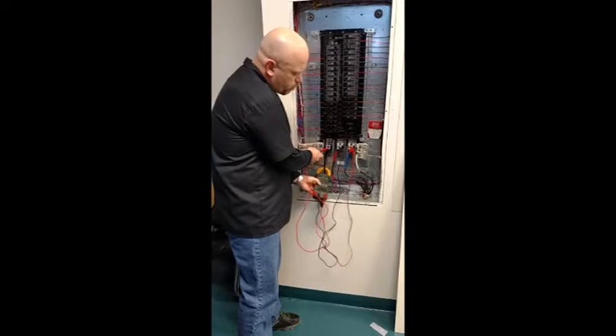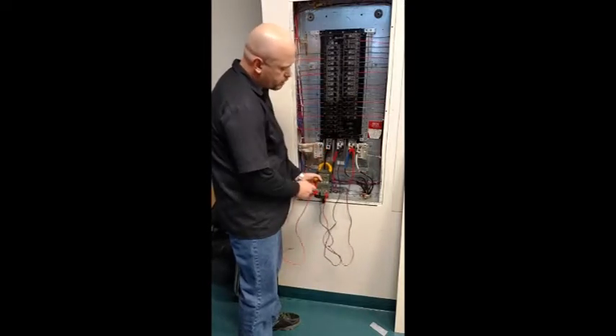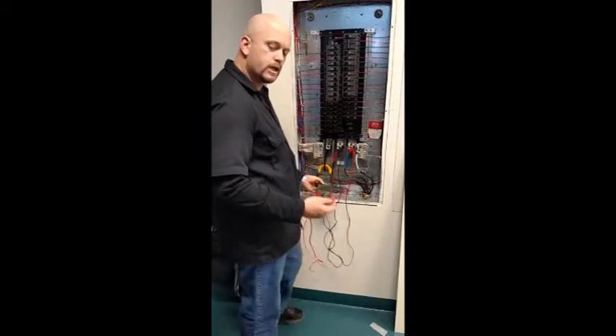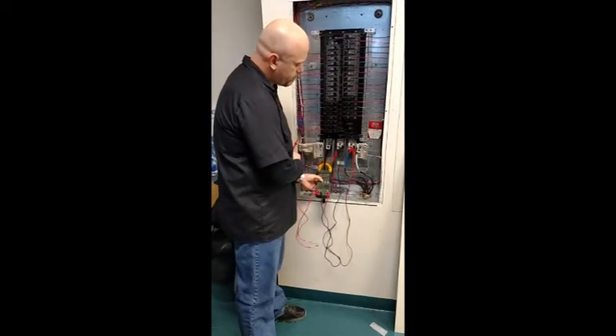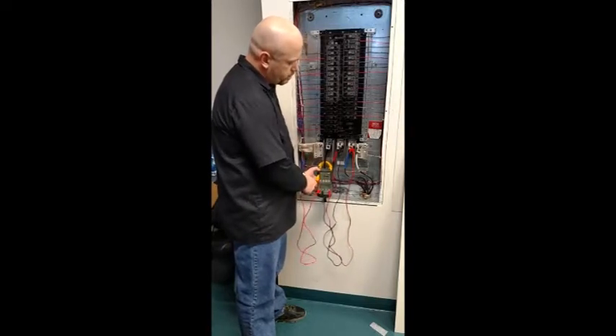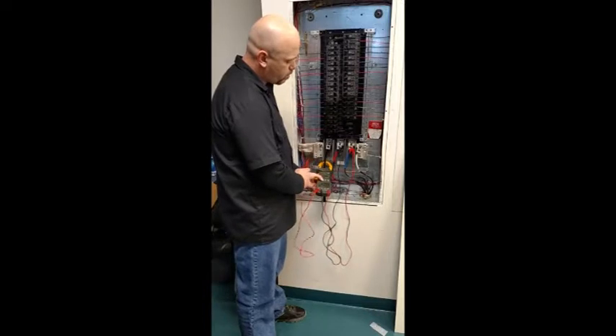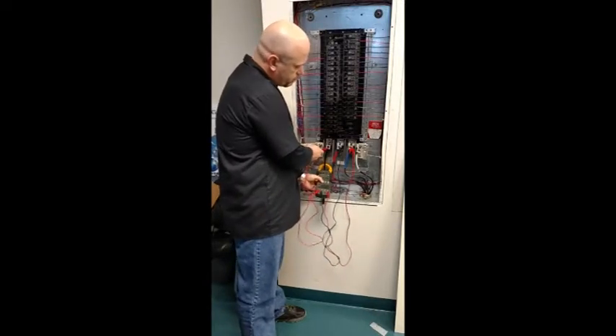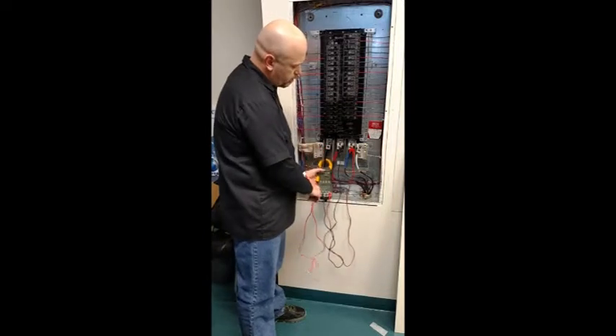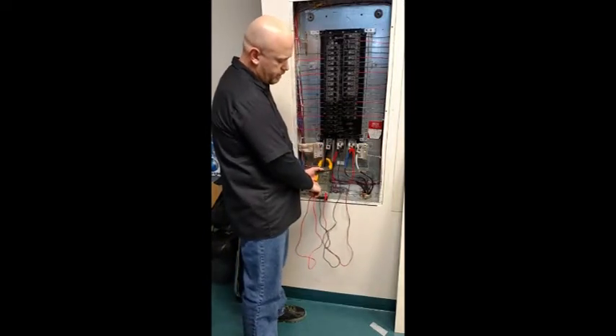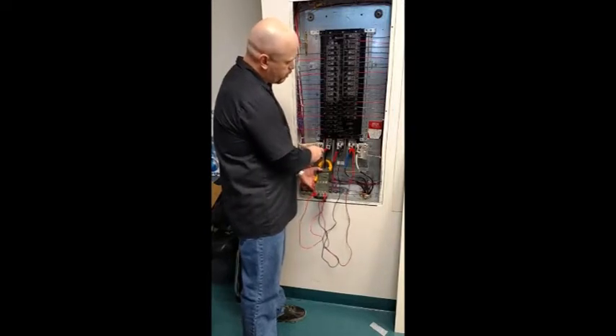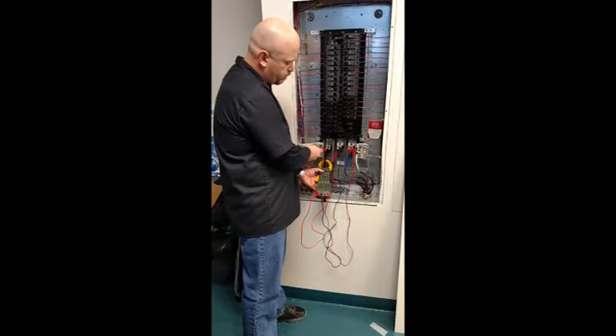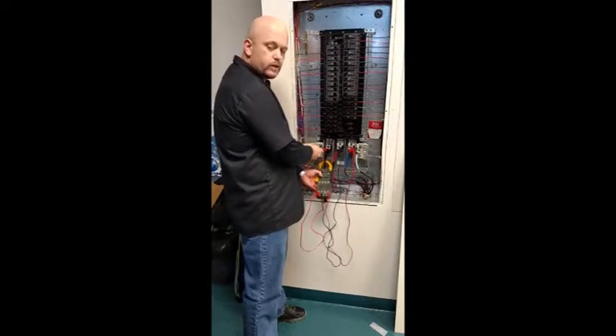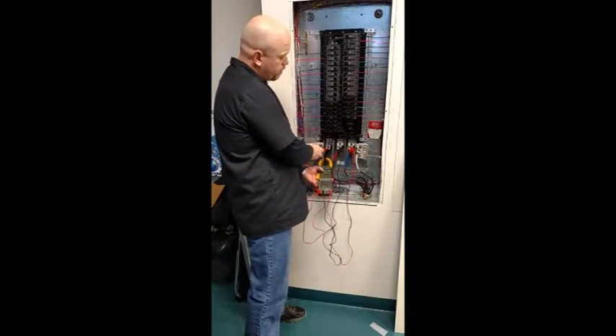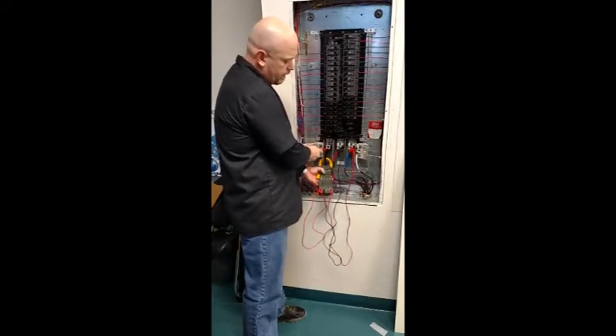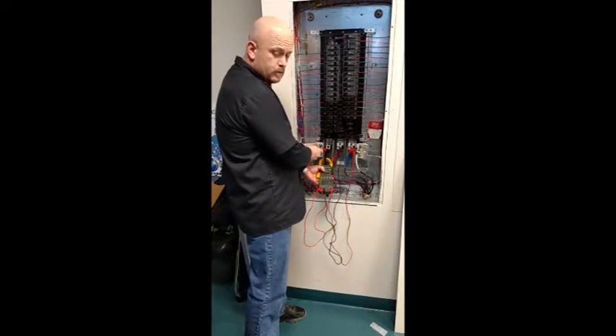Now the three-phase requires a couple extra steps. The initial reading that you get on this front screen will not actually tell you what the efficiency of the system is. You'll have to hit the watts button, which will be in the second row, in the second column over. And you'll have to punch that button twice. And on the screen you will see over in the middle of the left, it'll say cosine theta. And that will tell you that you're in a power factor measuring situation. And this will tell you what the phase relationship between all three phases is in a delta configuration. So, again, you'd want to record the volts, the amps, and the power factor.